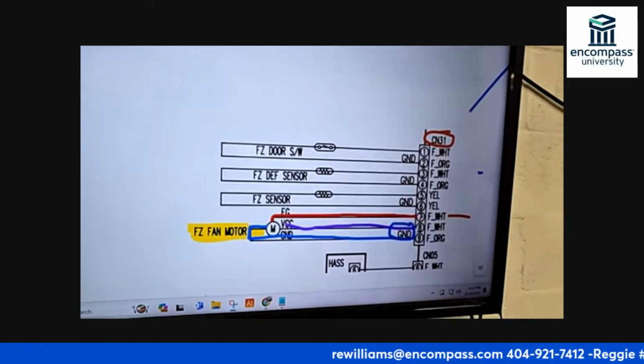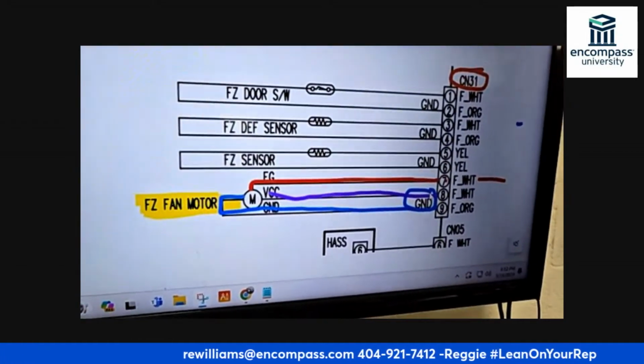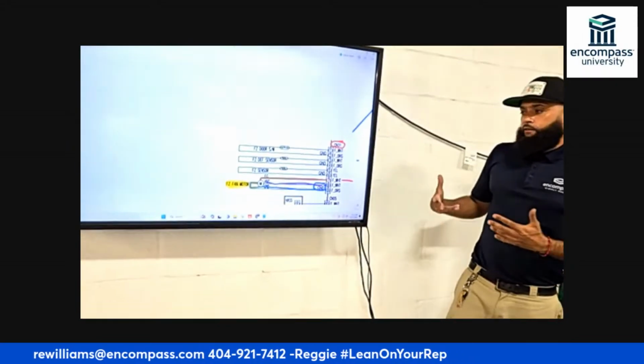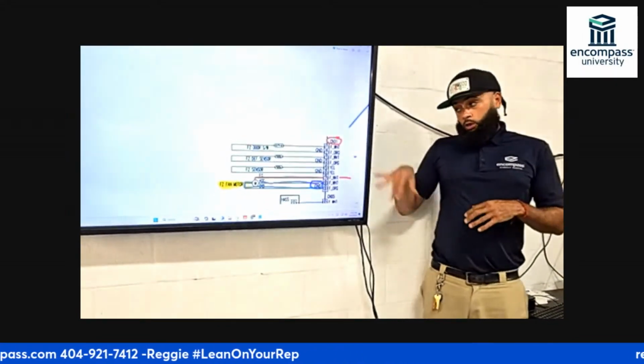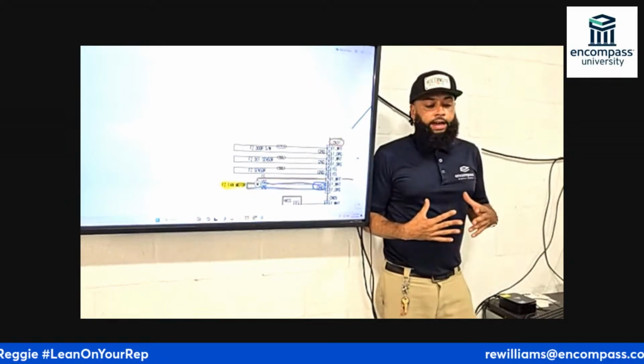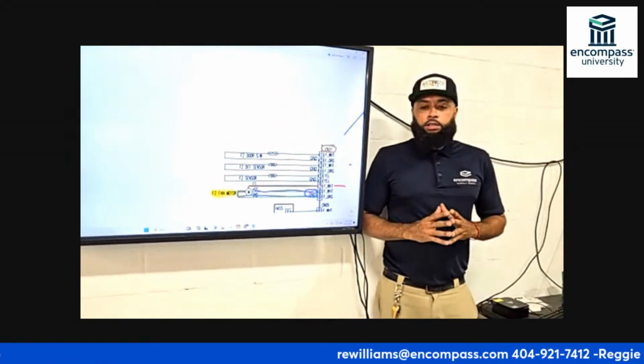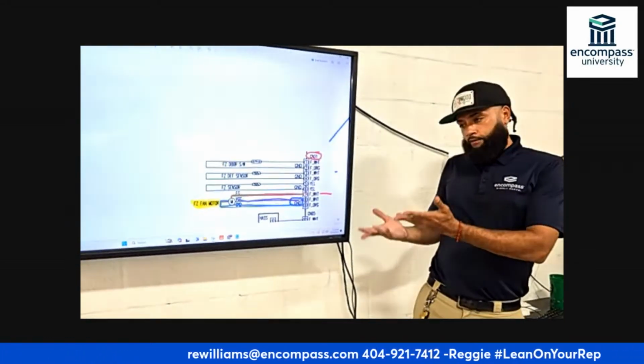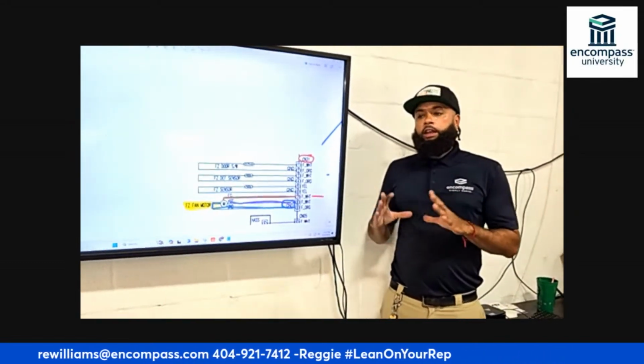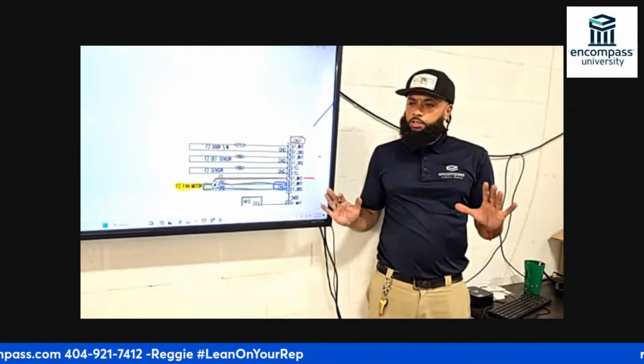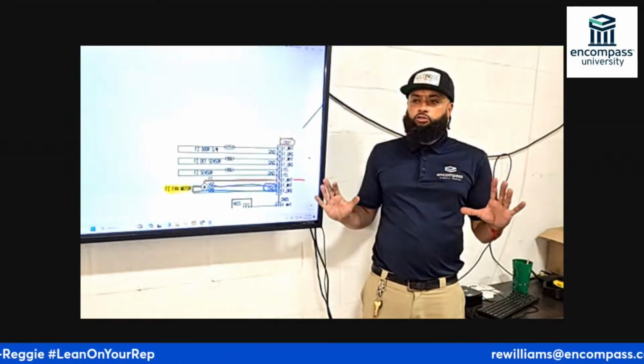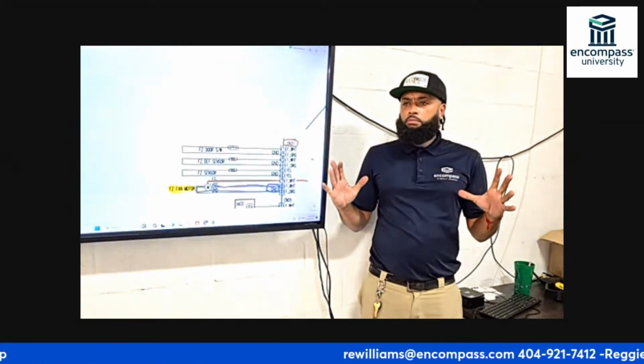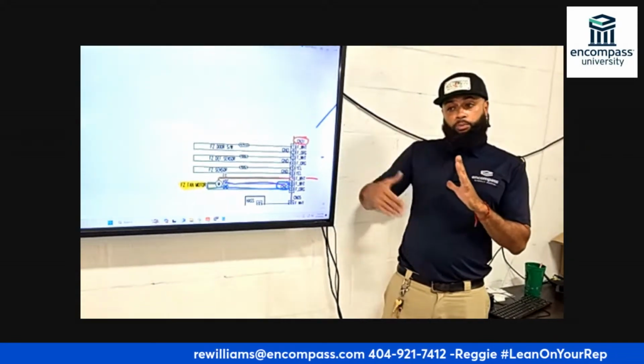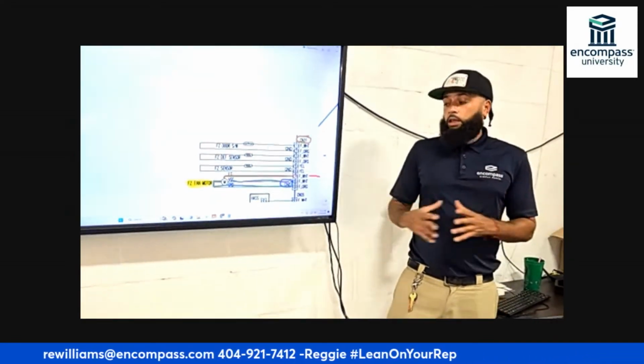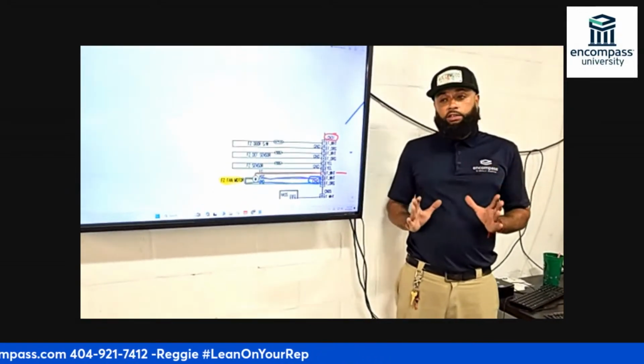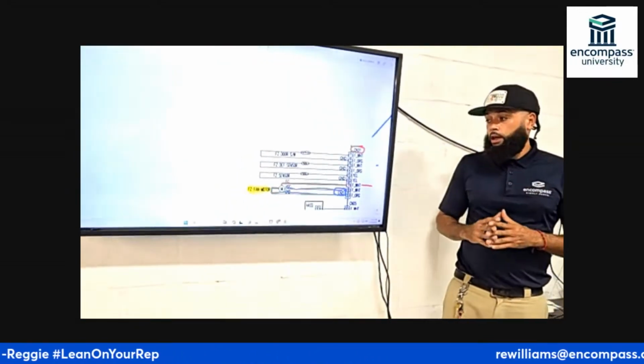That's my communication wire. Okay, take a step back. What am I communicating? Well, why does this fan communicate? Well, Samsung fans are very unique in the way they operate. The board will supply voltage to the fan, right? And if the fan, under normal circumstances, doesn't have any obstruction, it's not iced up, everything is good, there's nothing impeding the blade from rotating, typically it turns right on in about 7 to 12 seconds when the doors are closed.